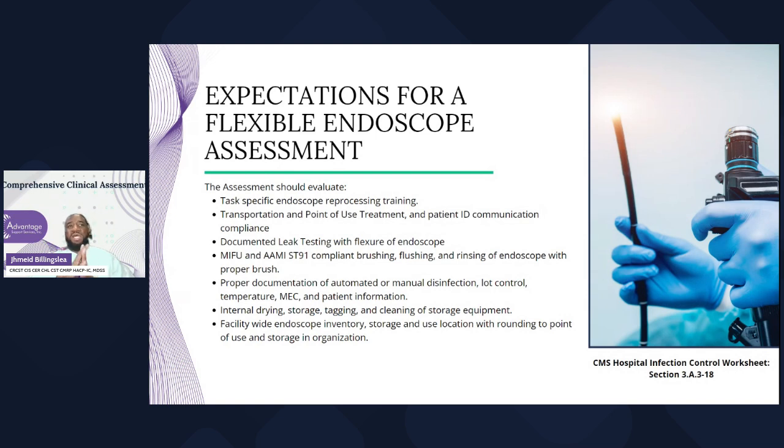Do we have proper documentation of automated and manual disinfection, lot control, the temperatures, the minimum effective level, and patient information, right? And that goes back to the transportation. If you don't have a sticker during transportation, I don't know how you're going to properly document, whether it's in an AER or a manual process.